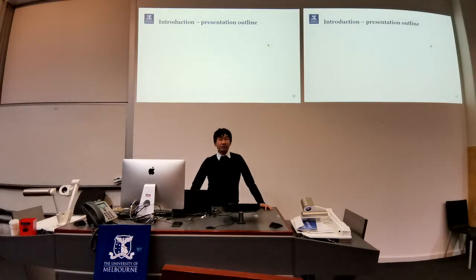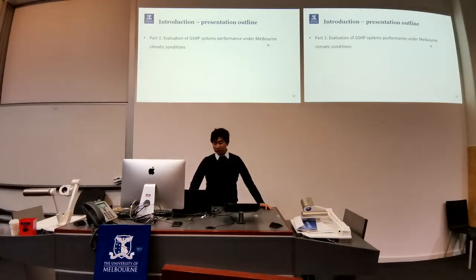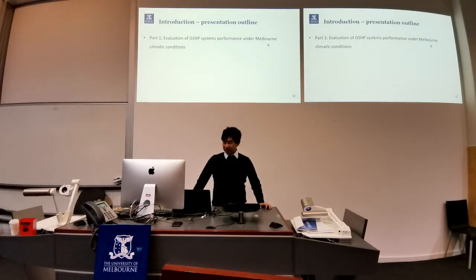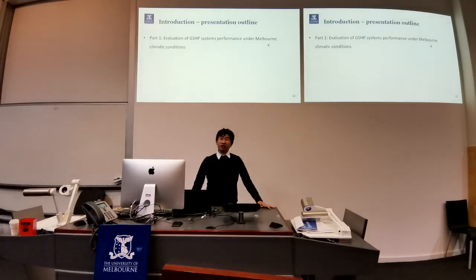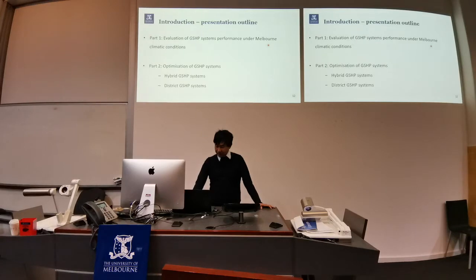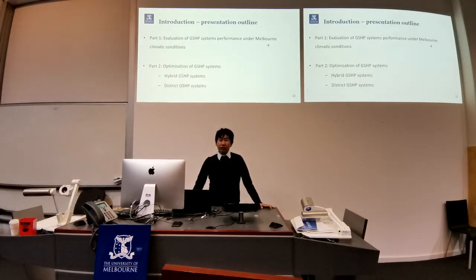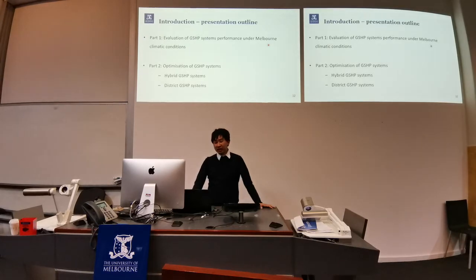Corresponding to the research objective, this presentation is divided into two sections. The first part is about our monitoring project, where we monitor the performance of some ground source heat pump systems around the state. The second part is about improving the viability of ground source heat pump systems. This is through the use of hybrid or district systems. A hybrid system is when ground source heat pump systems are used with conventional systems, whereas a district system is when individual ground source heat pumps in nearby buildings are combined together.